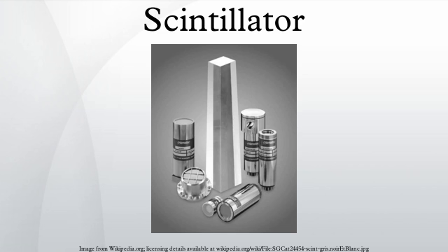LaBr3(Ce), a better alternative to NaI(Tl). Denser, more efficient, much faster, having a decay time of about 20 nanoseconds, it offers superior energy resolution due to its very high light output. Moreover, the light output is very stable and quite high over a very wide range of temperatures, making it particularly attractive for high-temperature applications. Depending on the application, the intrinsic activity of 138La can be a disadvantage. LaBr3(Ce) is very hygroscopic.